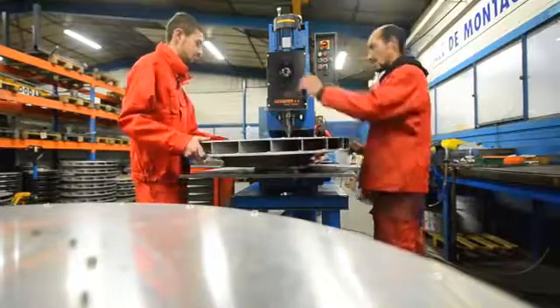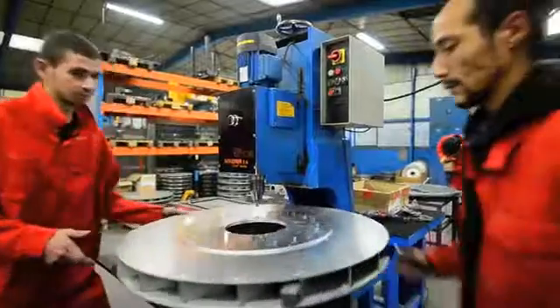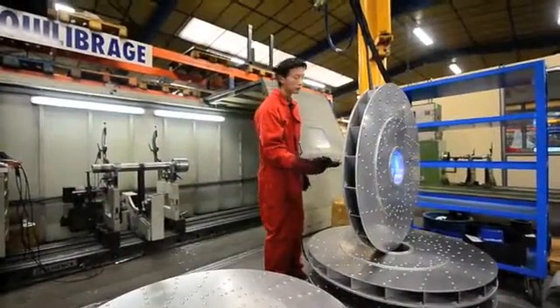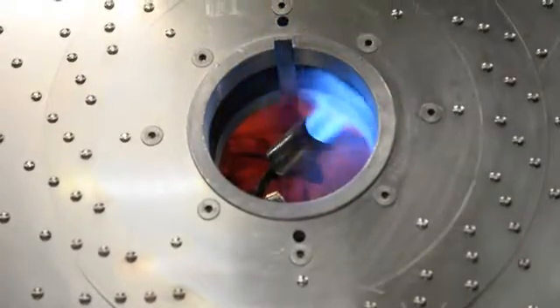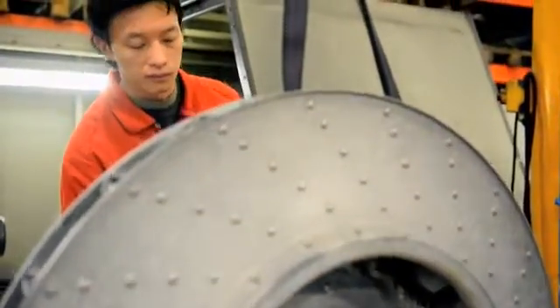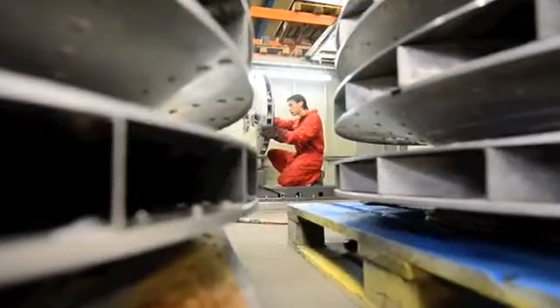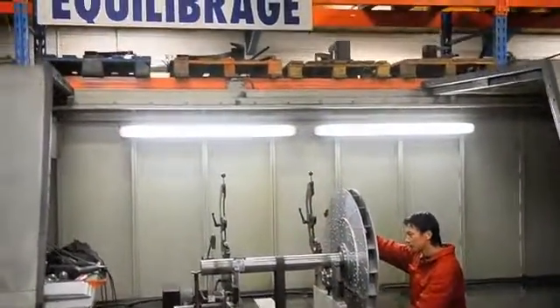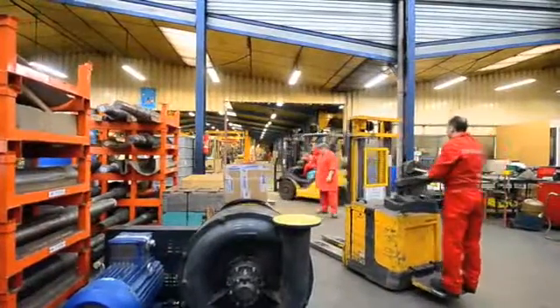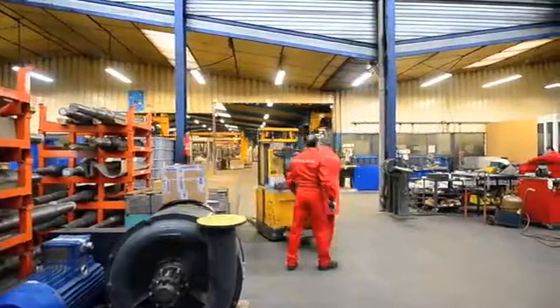Bearing housings. The bearings are mounted in independent cast iron housings. These housings are securely bolted to the inlet and outlet heads and allow easy access for routine maintenance. The bearings are the only running contacts between the shaft and casing. Sealing of the housing is by graphitized straps, or on the larger machines by segmented carbon rings, which are held together by a stainless steel spring. Leakage is thus reduced to a minimum with this type of seal.